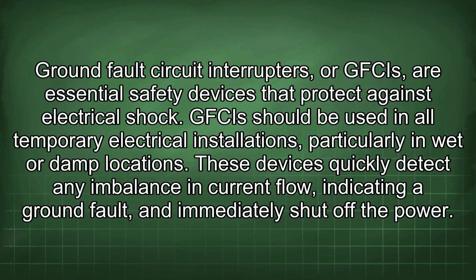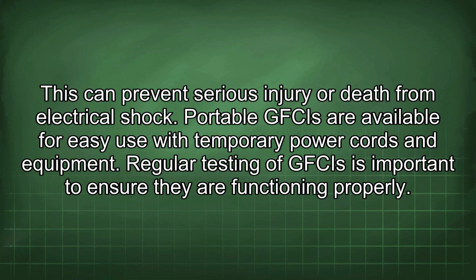Ground fault circuit interrupters, or GFCIs, are essential safety devices that protect against electrical shock. GFCIs should be used in all temporary electrical installations, particularly in wet or damp locations. These devices quickly detect any imbalance in current flow, indicating a ground fault, and immediately shut off the power. This can prevent serious injury or death from electrical shock. Portable GFCIs are available for easy use with temporary power cords and equipment. Regular testing of GFCIs is important to ensure they are functioning properly.